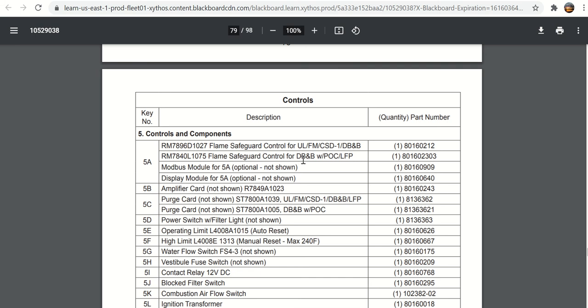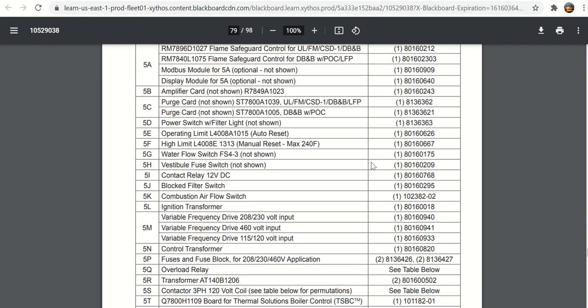You have to have a full function programmer for that. And this is low fire proof, LFP. That is the kind of stuff, or the features, you would get with a full function programmer. What we looked at on the wiring diagram was a 7896D traditional flame safeguard, considered an advanced primary control, but they also offer it with the full function programmer, the RM7840L, if you required to have POC and low fire proof, proof of closure and low fire proof of start.